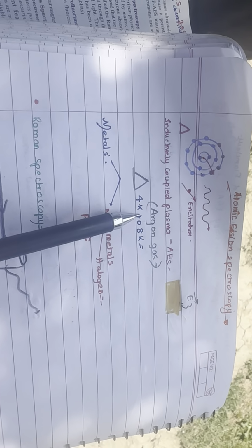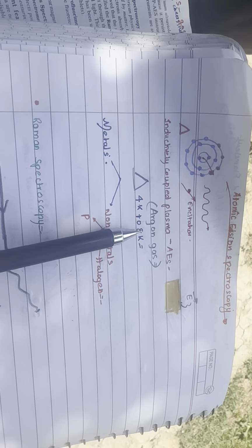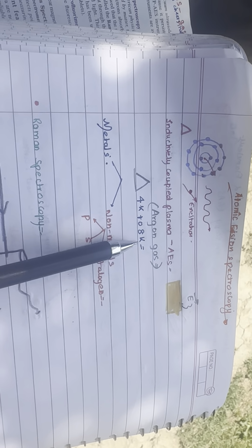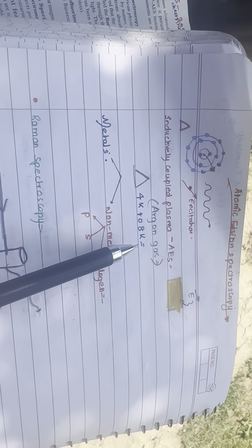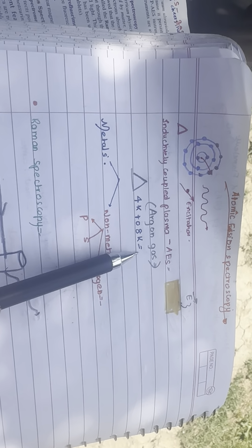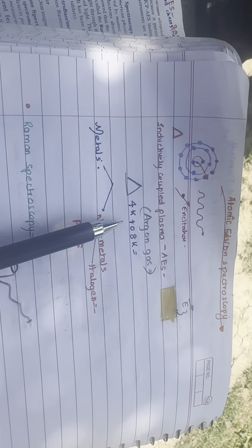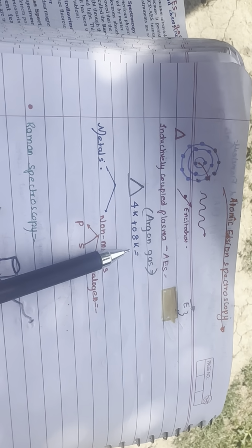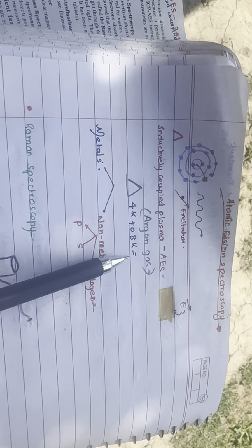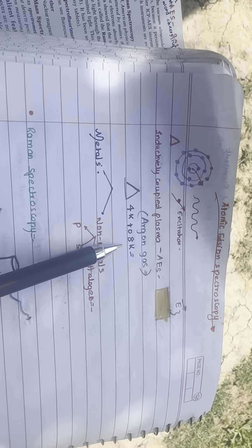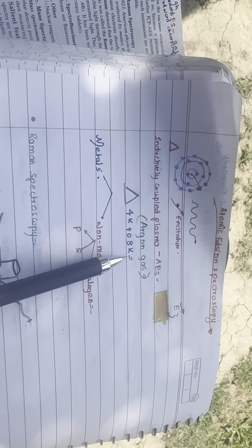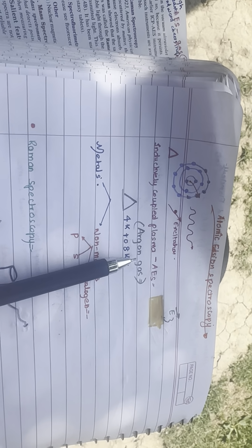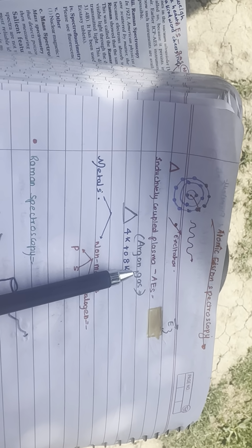The temperature ranges from 4000 to 8000 K. This plasma is used as the atomization and excitation source. The sample is introduced into the plasma. Its molecules immediately collide with electrons and charged ions in the plasma, and the sample is broken down into respective atoms. Electrons in individual atoms gain energy from the plasma to move to a higher level. As they return to the original position, they emit radiation with the characteristic wavelength of the element involved.